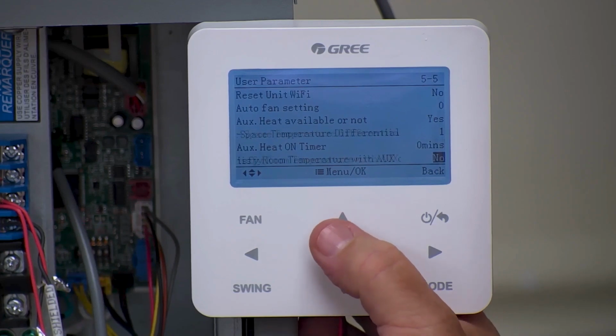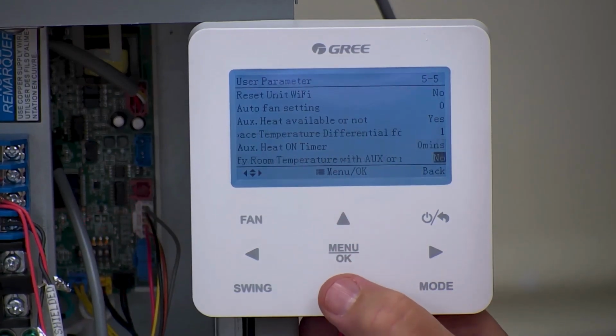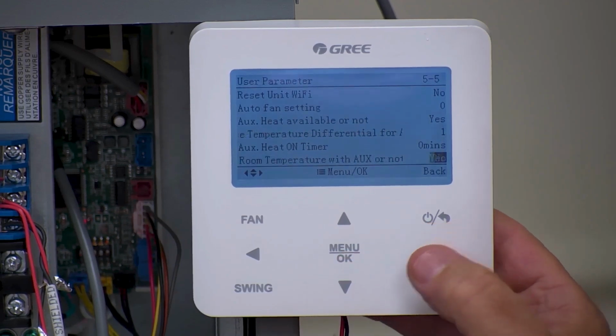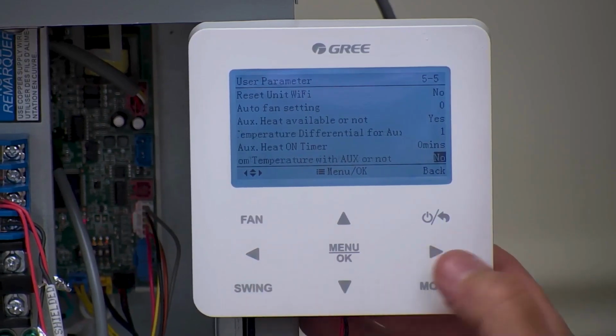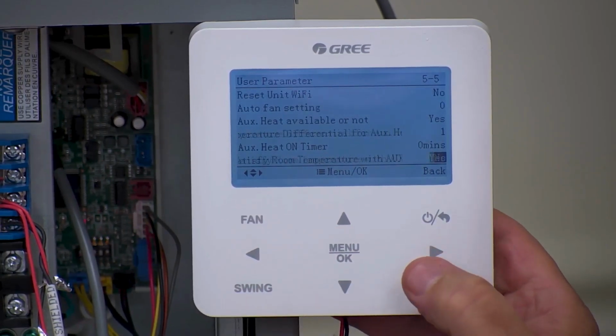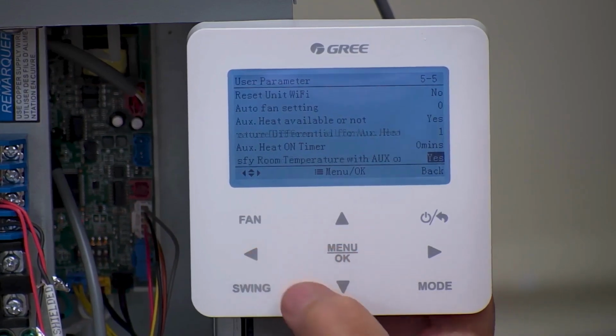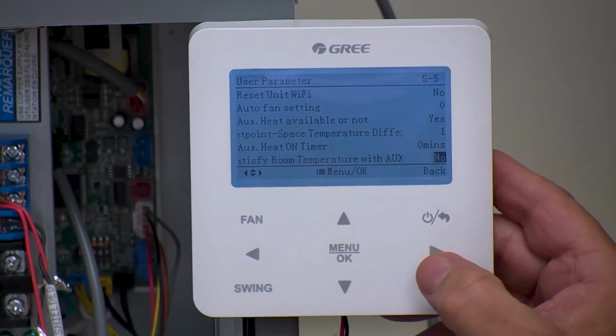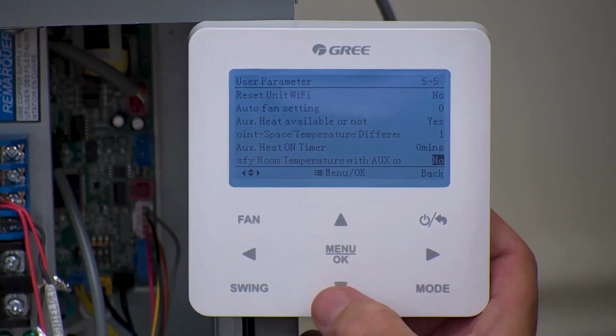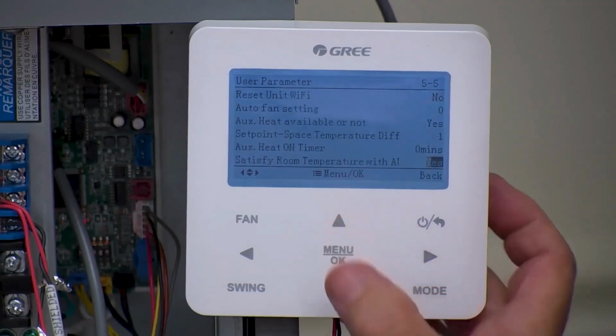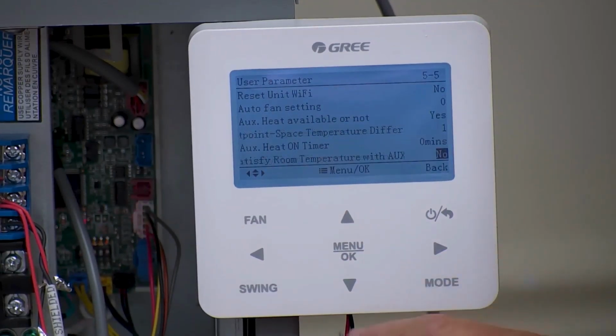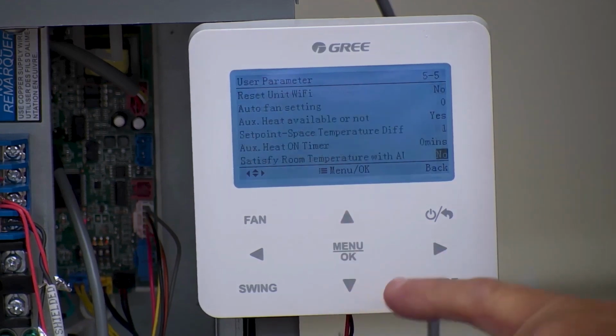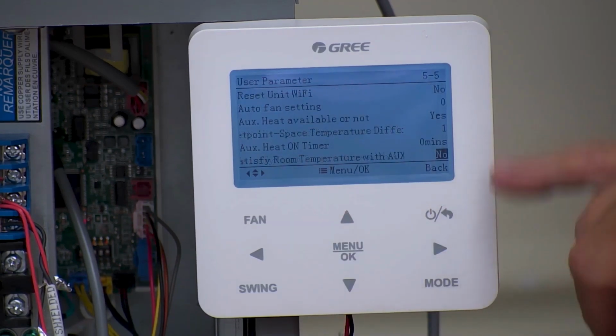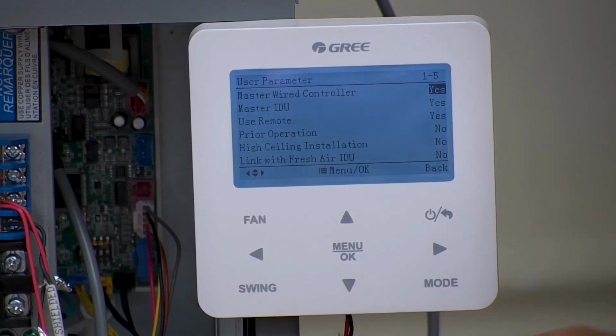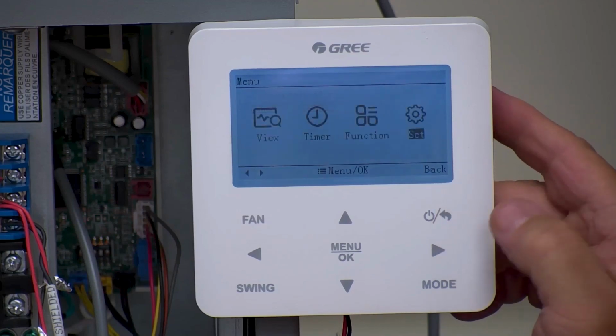We also have the satisfy room temperature with auxiliary heat. Again, I already kind of talked about that. You can set this to yes or no. Just remember when you change the setting, after you change it, once I set it to yes, I have to hit menu. And then if you see, I'll go back to it, it still says yes. If I go to no, and then I save it, and then I go away from it and go back to it, it should still say no, and it does. Okay, so you got to save it after you set it, just so you know. So there's your 3 settings you got to set. That's all there is to it. And then we can go back to the main screen.